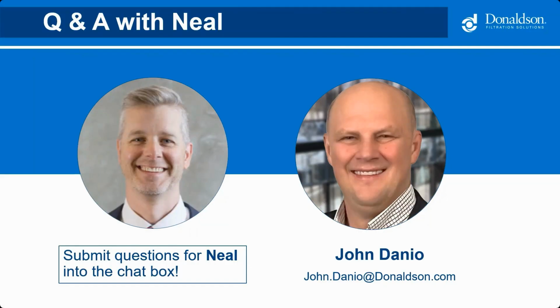Excellent. So this is kind of from the beginning of the webinar. We're talking about hoods, I think mostly what these are talking about, and general system design. So the first question is, do we need redundancy for the blower? I'm not sure I understand the question. Like would you need a second blower, I guess, and I don't think you do, right? If you size it, no, typically if it's sized right, the one fan is all that you need.